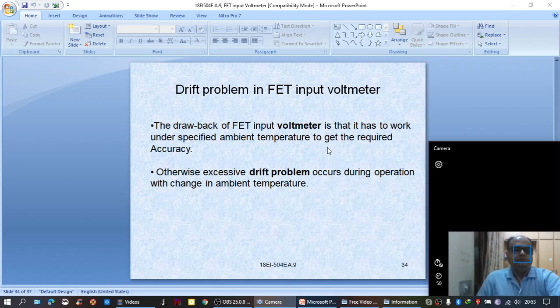Say, for example, 25 degrees to 40 degrees or 0 to 40 degrees. A range is given by the manufacturer. If we are using the instrument at high temperatures or low temperatures, there would be a drift in the voltage. There would be a change in the resulting current in the circuit, and the measurement also will be slightly in error.